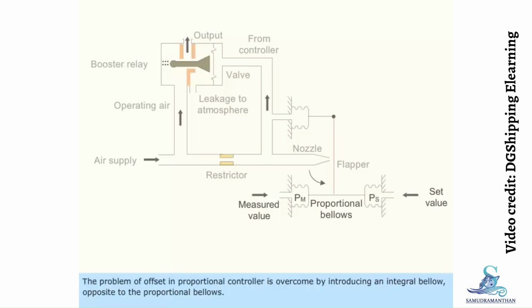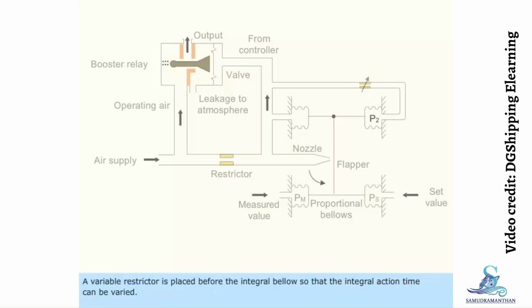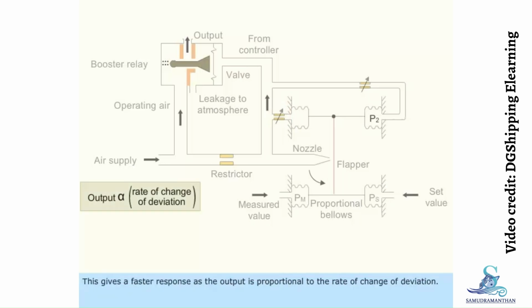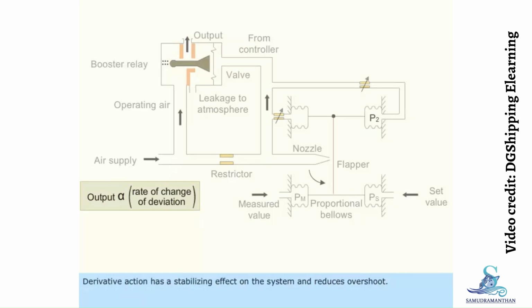The problem of offset in a proportional controller is overcome by introducing an integral bellow opposite to the proportional bellows. A variable restrictor is placed before the integral bellow so that the integral action time can be varied. The additional integral bellow will introduce a positive feedback to raise the pressure P2 at a rate dependent on the deviation. Integral action will continue until the deviation ceases and there is no offset. Derivative action is obtained by placing a variable restrictor before the proportional bellow. This gives a faster response as the output is proportional to the rate of change of deviation. Derivative action has a stabilizing effect on the system and reduces overshoot.